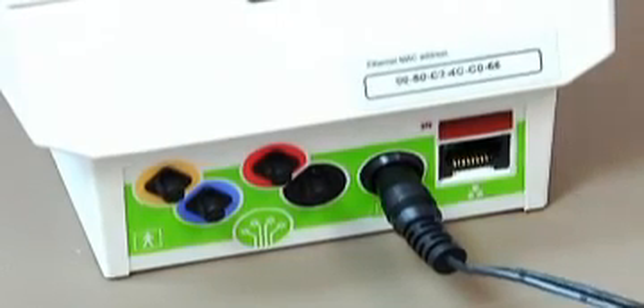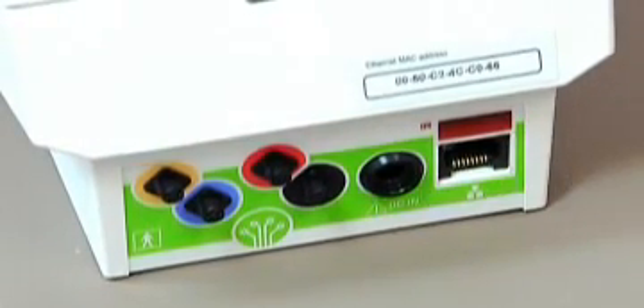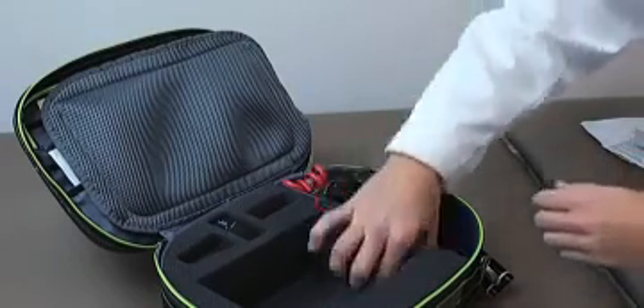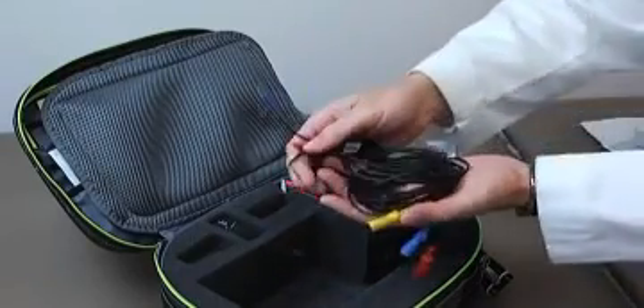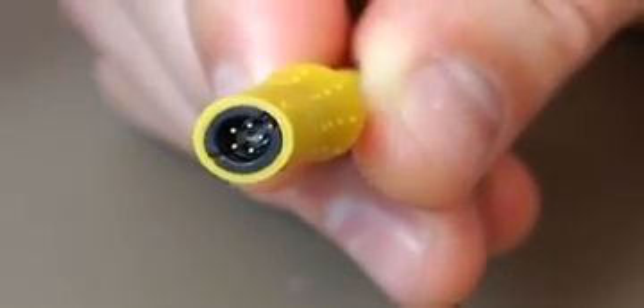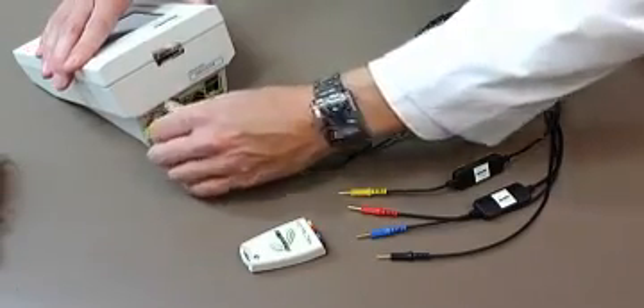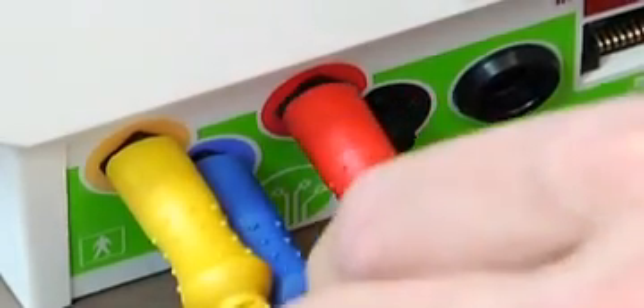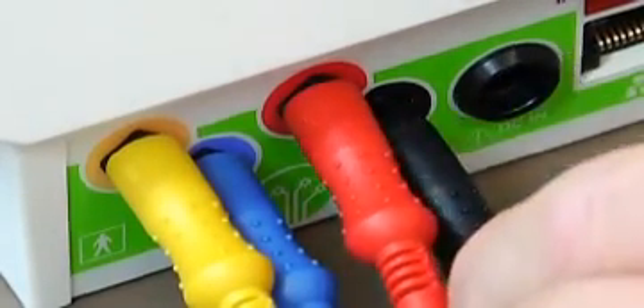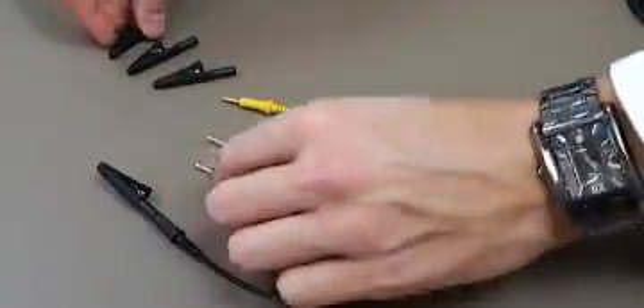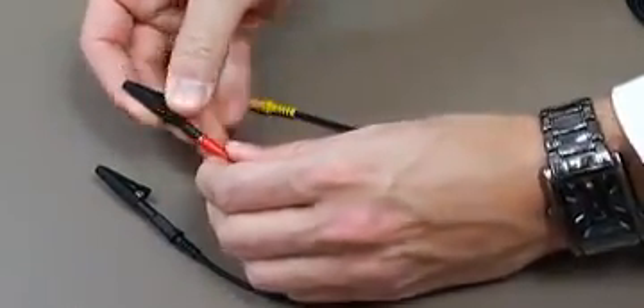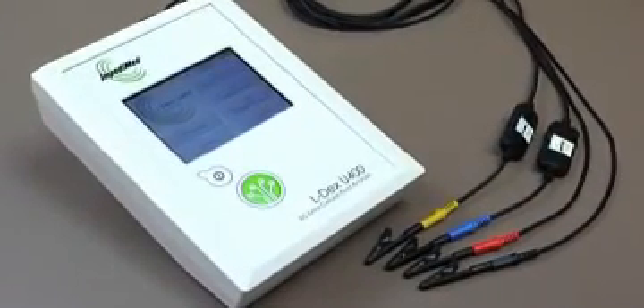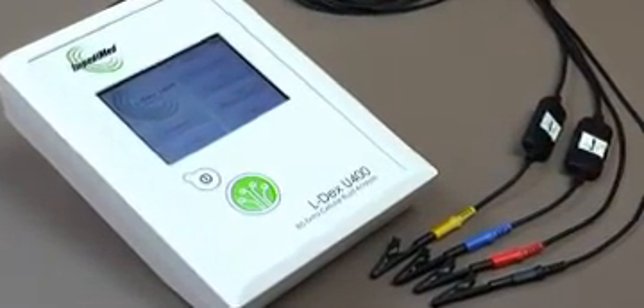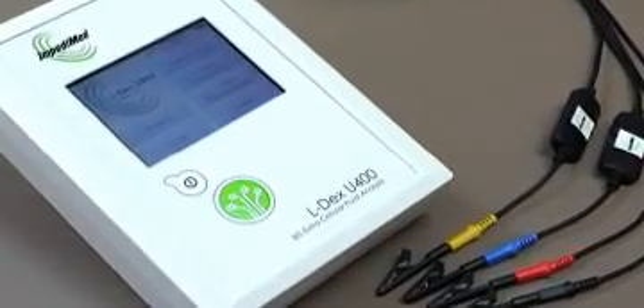When the device is charged and you are ready to take a measurement, remove the power cord from the device, as you cannot take a measurement while the device is plugged in. Remove the set of 4 leads from the soft carrying case. Plug the leads into the corresponding color-coded sockets using the arrow on the leads and the notches on the device as guides. Attach the provided alligator clips to the ends of the leads. The device is now ready to take a measurement. Ensure that you set aside 15 to 20 minutes to complete the measurement process, including software entry and physician review.